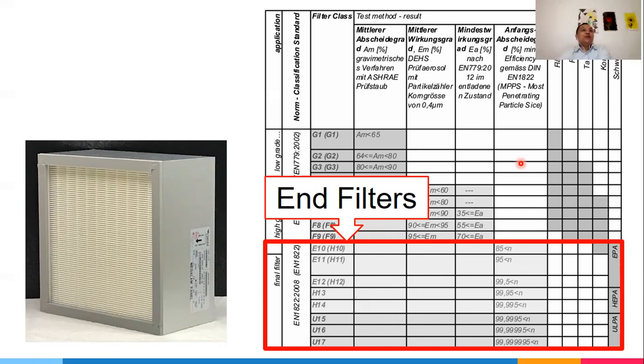It depends on your requirement. I have different applications that use end filters. One application is food and beverages, they also have a 100K clean room, but they chose to put the end filters in the room itself. There's also pharmaceutical, my operating laboratories, which require 10K, and the end filters are included in the AHU itself, so that during maintenance, when changing filters, they don't have to be inside the operating room.